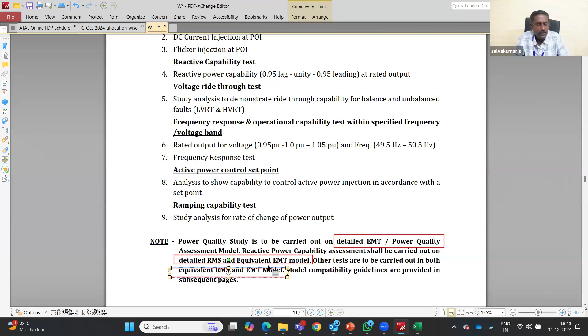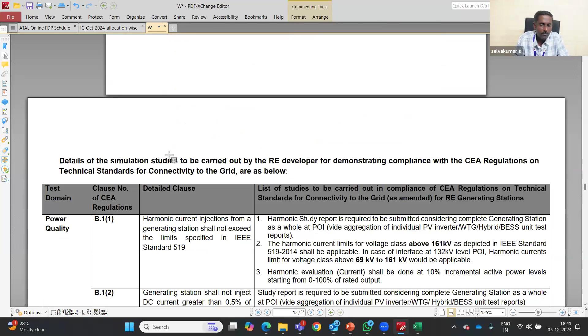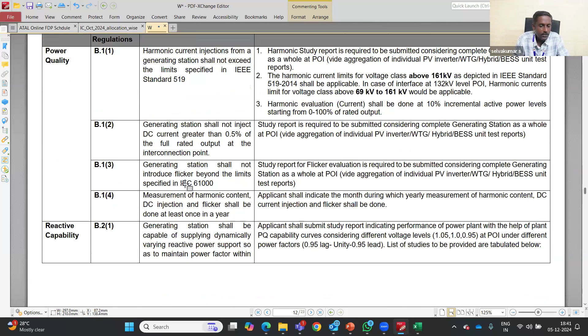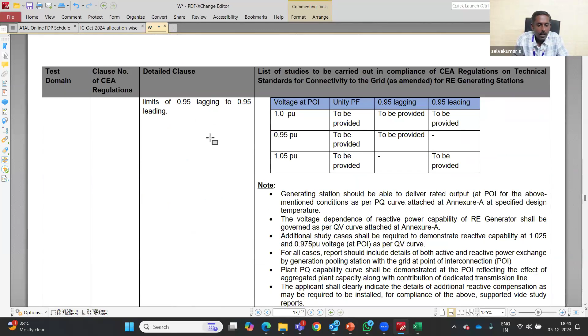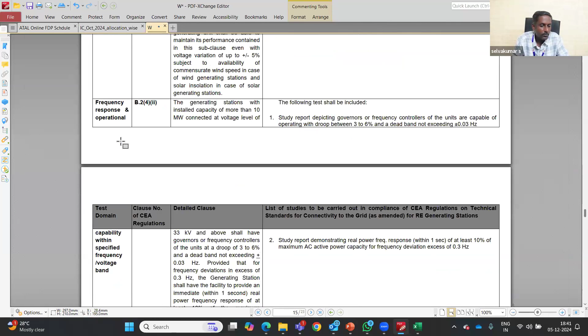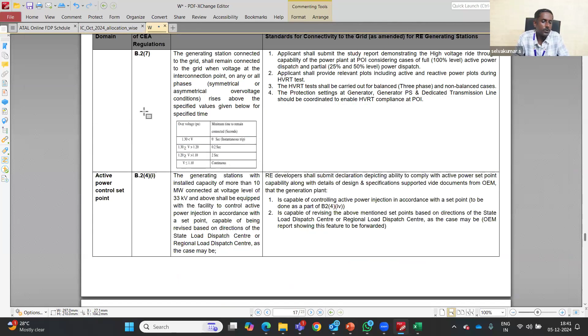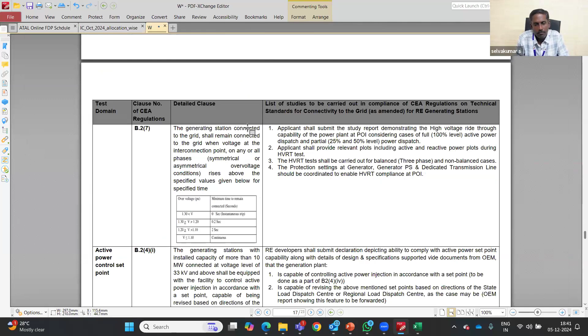If you're aware of this - what's the condition for power quality, like harmonics you need to meet, DC injection you need to meet, flicker you need to meet, reactive power capability at various grid voltages, and frequency response ride through - if you're aware of all these things, then you'll be able to do these grid compliance studies.